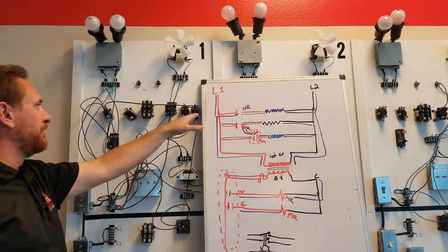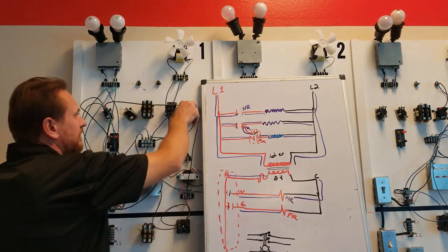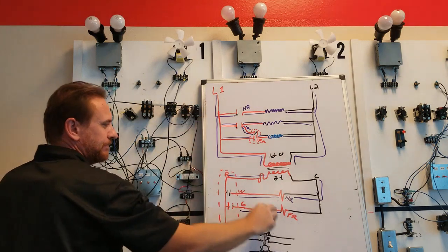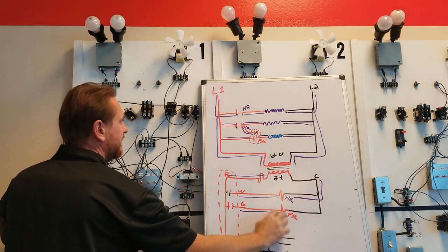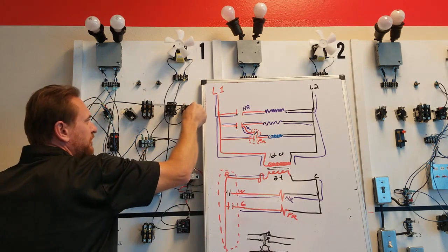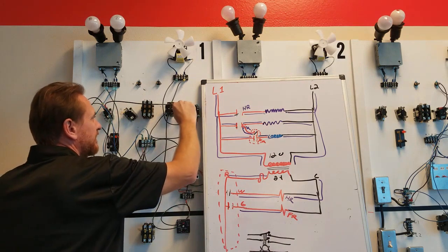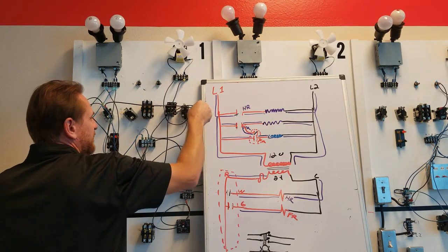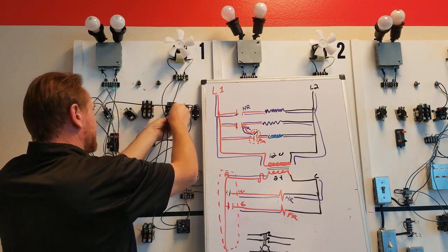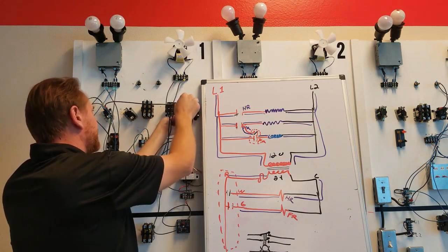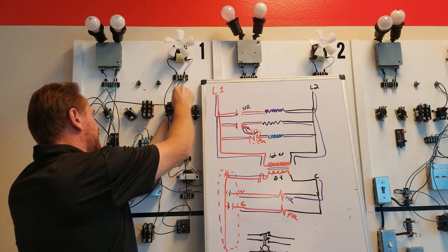We're going to move it from this relay over here to this relay. 24 volts was at the bottom. That's my 24 volts, sorry, here and here. So we're going to move it over to what we know is a load, which was here. And we're going to move this one over to here. We're going to swap it because my wires are too short. Alternating current, doesn't matter which one's which, as long as it's both on the load side.